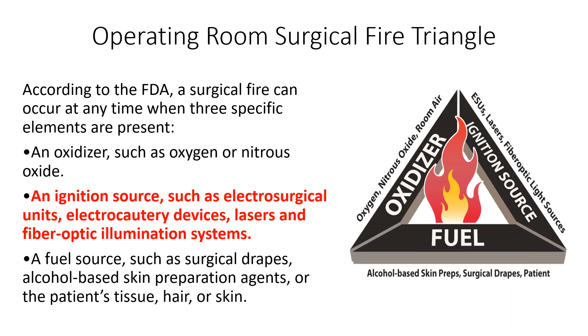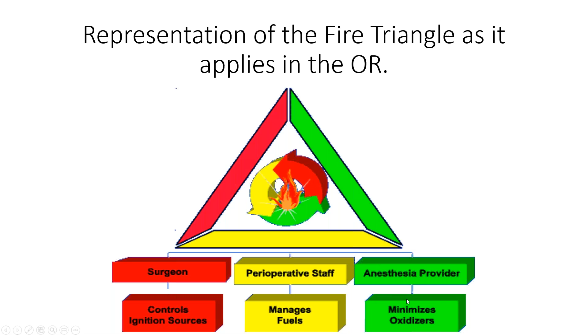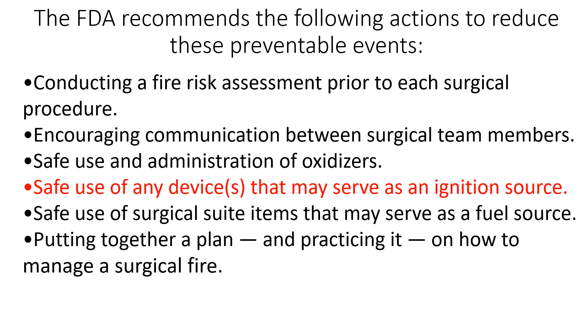And here's a representation of who manages what. So we know that the surgeon controls the ignition source, the perioperative staff manages the fuel, and the anesthesia provider controls the oxidizer, oxygen and nitrous oxide. So FDA recommends the following actions to reduce this preventable event: conducting a fire risk assessment prior to each surgical procedure, encouraging communication between the surgical team, such as a huddle or timeout, safe use of anesthesia, and we really in this are going to talk about ignition source, so that's safe use of any devices that may serve as an ignition source, and safe use of surgical suite items that may serve as a fuel source. And you need to obviously put a plan together, practice it, and know how to manage a surgical fire.